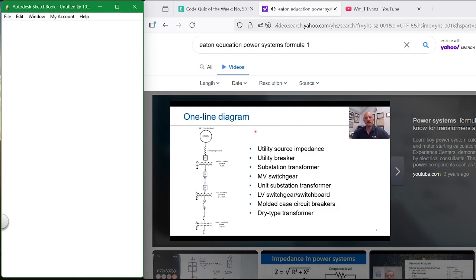But if we have the one line, like in this case, we can calculate and we can use the utility source impedance, the utility main breaker, substation transformer, medium voltage switchgear, like we show in the middle, unit substation transformer, for example, and then low voltage switchgear or switchboards, and then molded case breakers and dry type transformers down through the system. So all of that equipment with its proper information on the one line is going to be super helpful to doing your fault analysis and your load flow calculations and all of the things you'll do as an engineer or consultant.